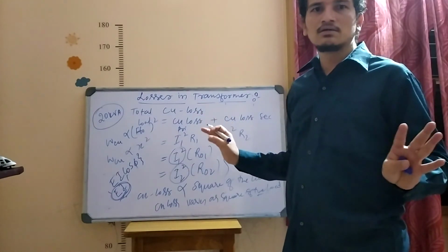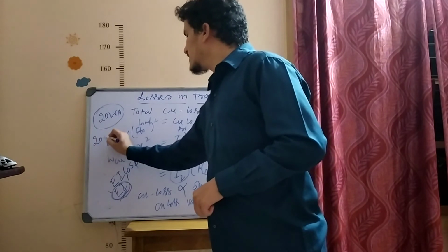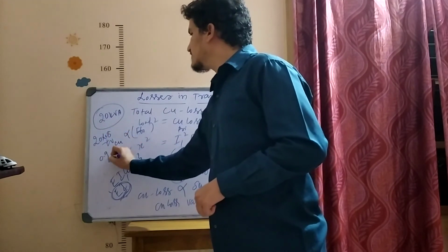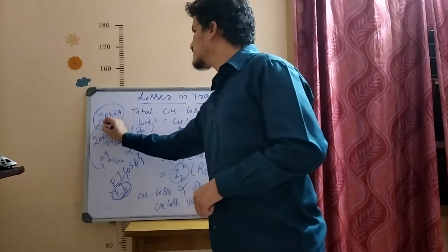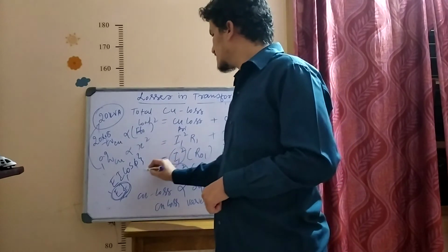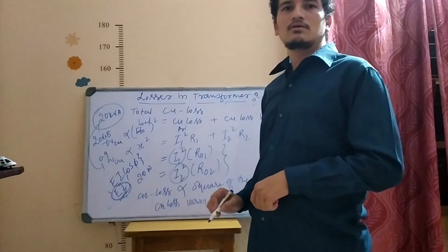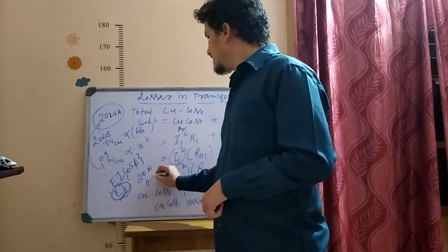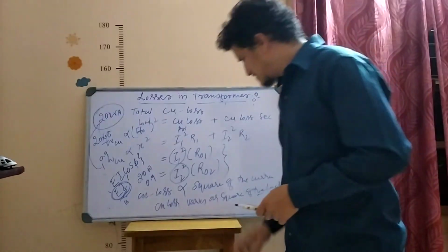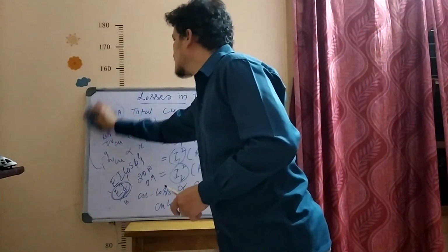Beyond that it cannot transfer. Means you can connect a 0.8 or 0.9 power factor load, and at unity it is 20 kVA, either lagging or leading. If you connect a unity power factor load, then it is 20 kW. If you connect 0.9, it may be around 18 or 19, like that. So this is all about why it is represented in kVA.